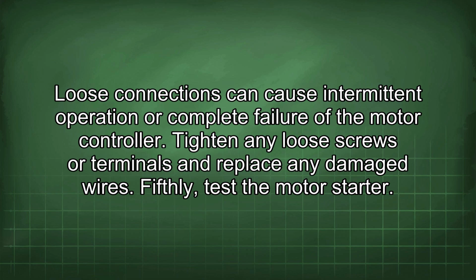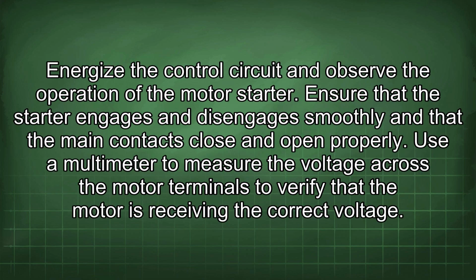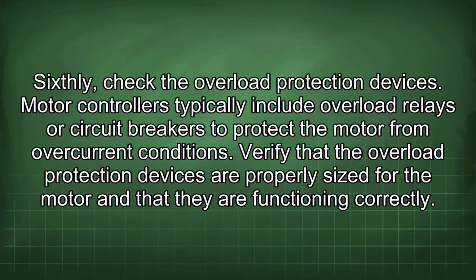Fifthly, test the motor starter. Energize the control circuit and observe the operation of the motor starter. Ensure that the starter engages and disengages smoothly and that the main contacts close and open properly. Use a multimeter to measure the voltage across the motor terminals to verify that the motor is receiving the correct voltage.